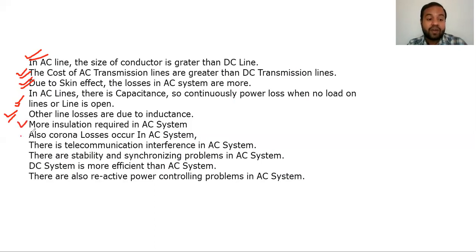Corona is also present in case of an AC system, and as I have already told you, corona loss is proportional to frequency. Since the DC frequency is zero, corona loss will be lesser in a DC system than in an AC system.